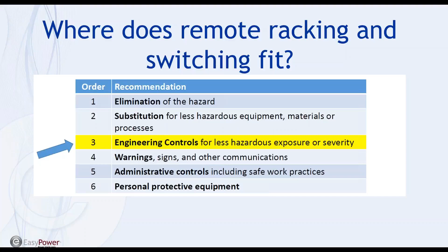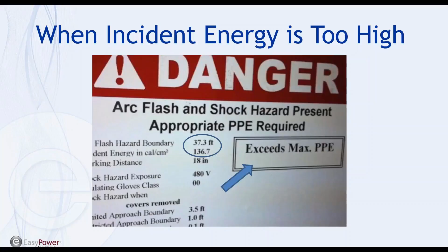So I want to review some situations that may warrant remote racking and or remote switching. These would be ideal solutions, and this is limited. It's certainly not every situation out there. But first is when incident energy is too high. So here we're looking at an arc flash label, and you'll see that the boundary is 37 feet away, and incident energy here is over 136 calories. And the sticker says clearly exceeds maximum PPE. This is a great situation to bring in remote switching and remote racking whenever you can.